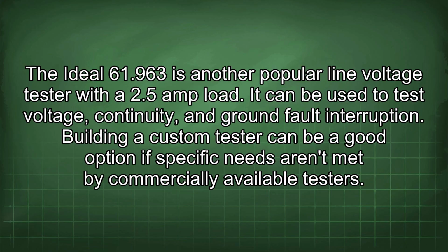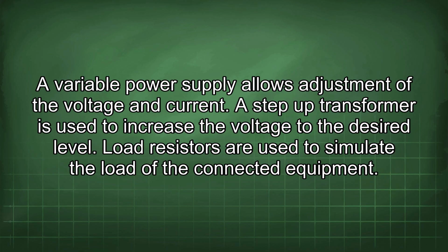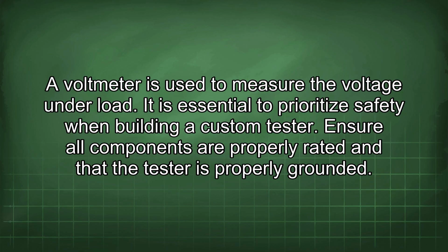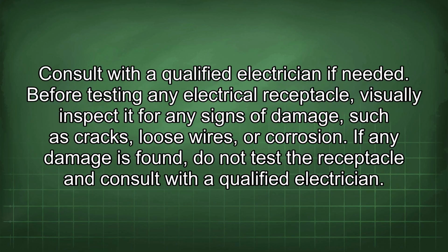Building a custom tester can be a good option if specific needs aren't met by commercially available testers. A variable power supply allows adjustment of the voltage and current. A step-up transformer is used to increase the voltage to the desired level. Load resistors are used to simulate the load of the connected equipment. A voltmeter is used to measure the voltage under load. It is essential to prioritize safety when building a custom tester. Ensure all components are properly rated and that the tester is properly grounded. Consult with a qualified electrician if needed.